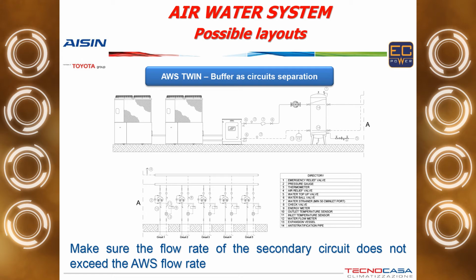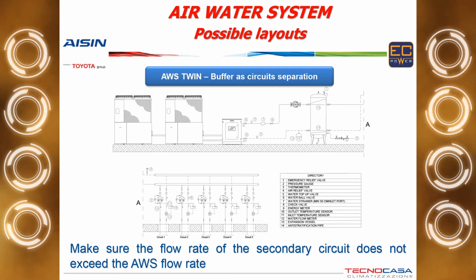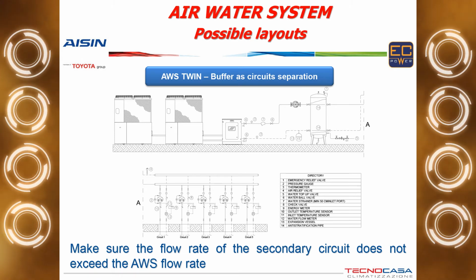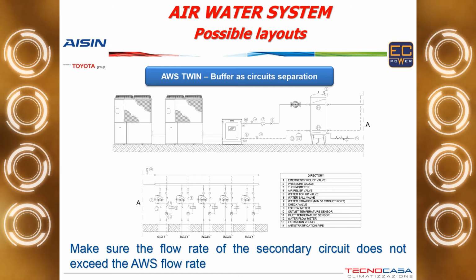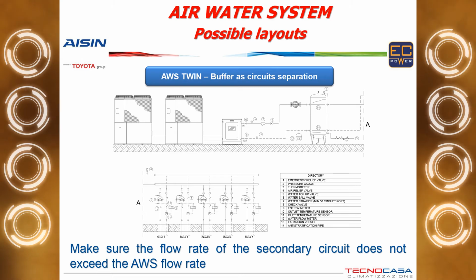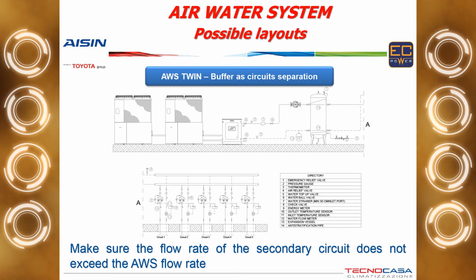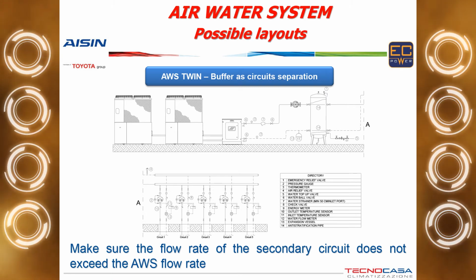This is what we suggest usually when we have to refurbish an existing system, so that you can also make sure that the dirt coming from the indoor system stays in the buffer tank and does not go into the new heat exchanger. In this case, you have to make sure that the flow rate of the secondary system never exceeds the flow rate of the primary system. And as you can see down here, this is very useful when you have multiple users and you wish to address the consumption of each user and sell the energy directly to the end user. So in this case, we can also calculate how much energy each one is using and address the costs user by user.